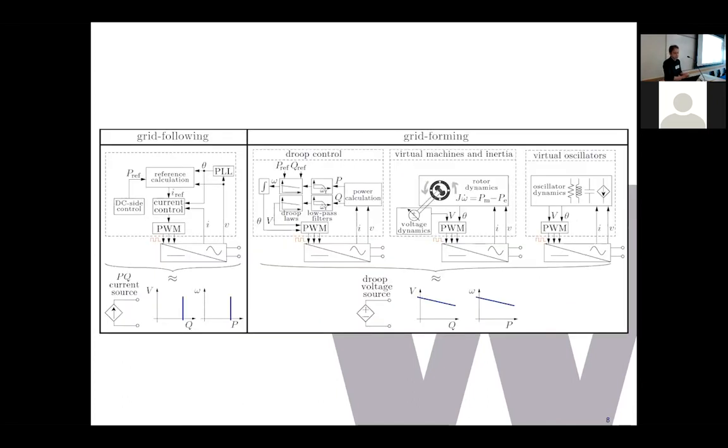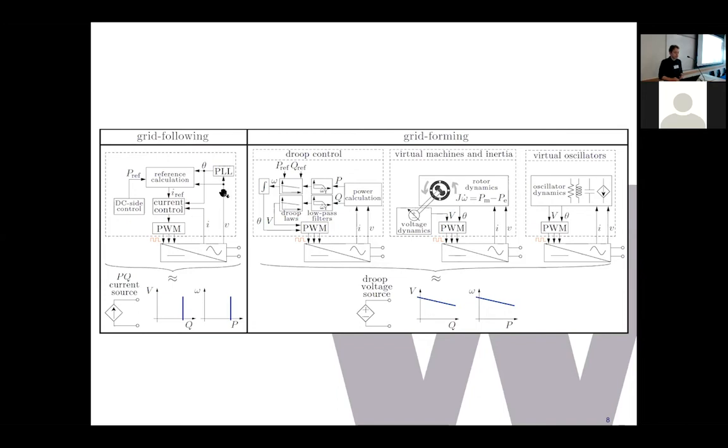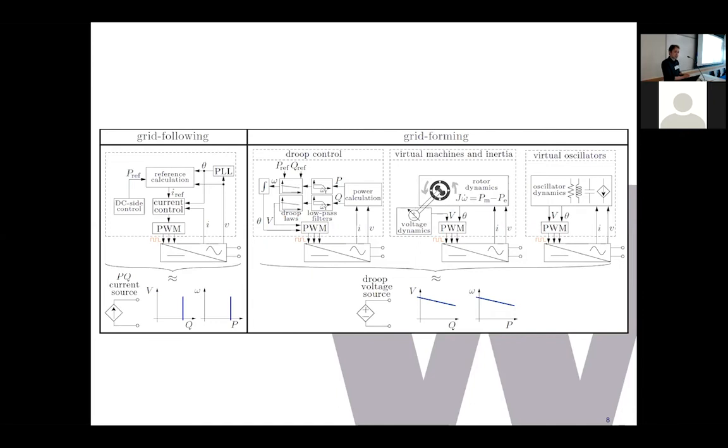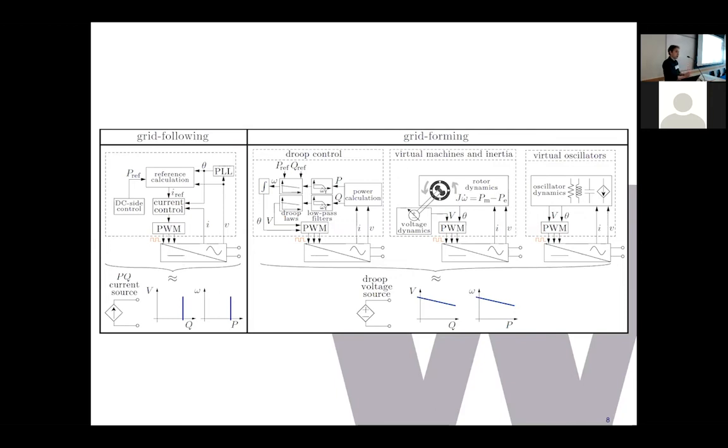Here's getting a little bit into the technical side. The left hand side here I am showing the conventional way that basically all power electronics on the grid today are controlled. The key piece of this is what I call this PLL, this phase locked loop. Right now it is not a settled question as to exactly what constitutes a grid following or grid forming inverter. For the sake of having a concrete way of defining things in our document, that was essentially our litmus test. If something has a phase lock loop, what that means is that it needs to track the grid voltage angle that it sees at its terminals. If it's using that as a primary function to dictate its timing it is a following unit. The phase lock loop is the heart of this following functionality.